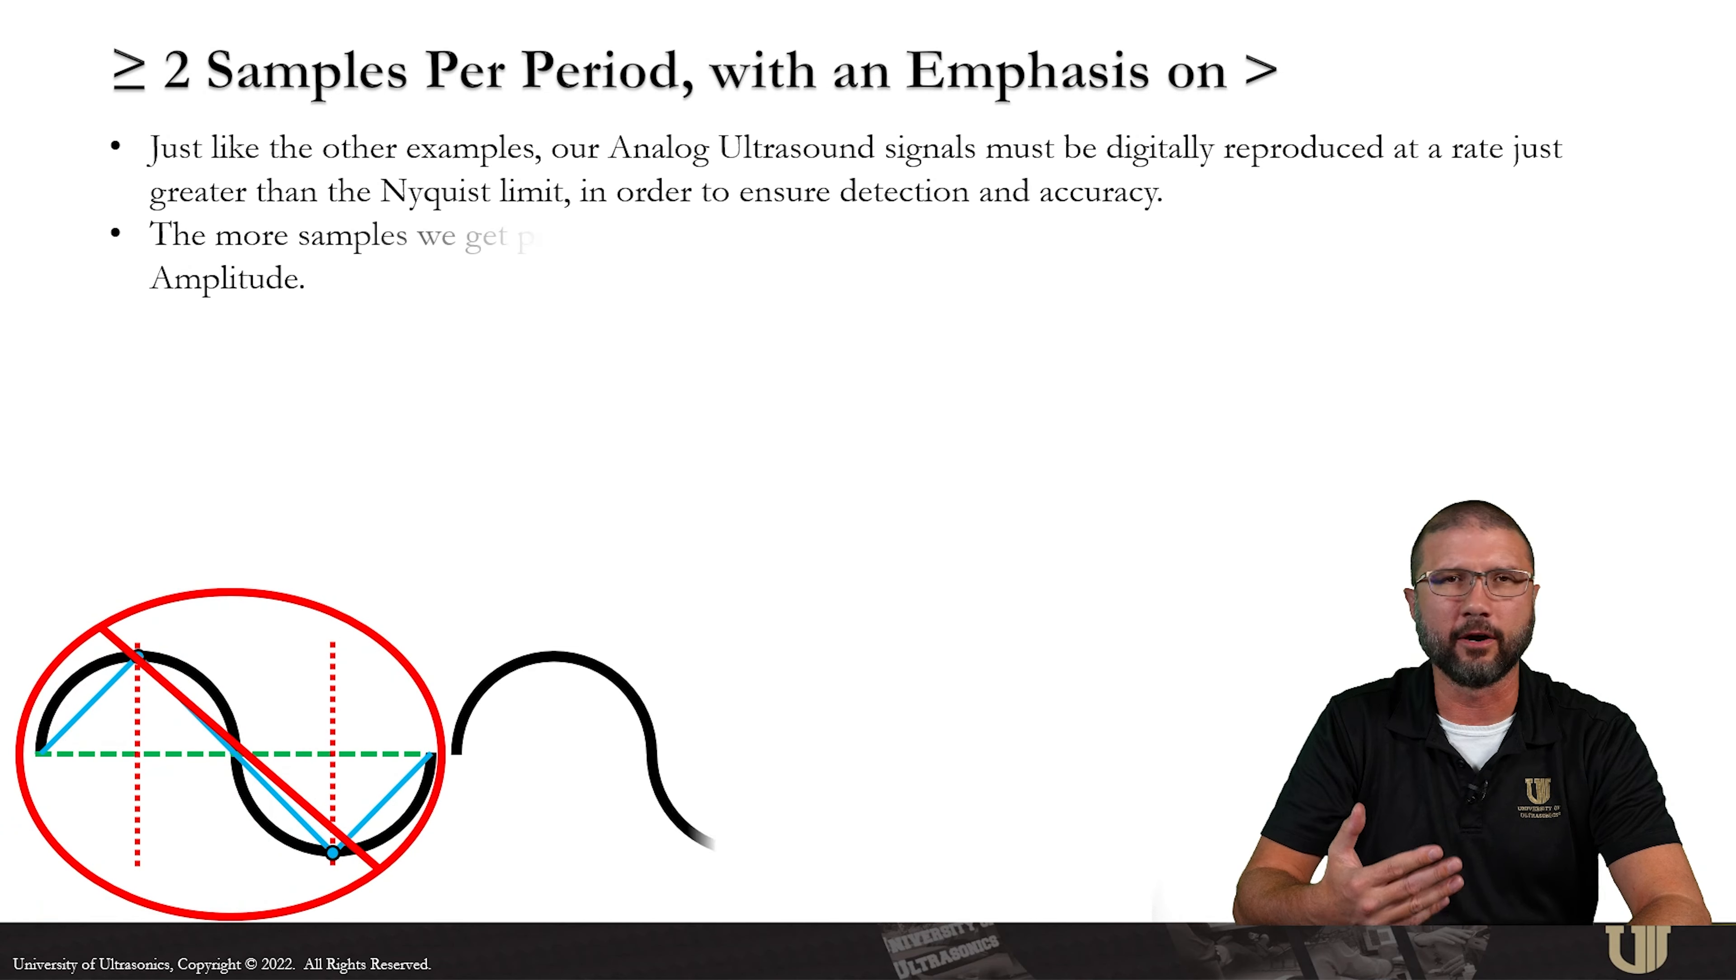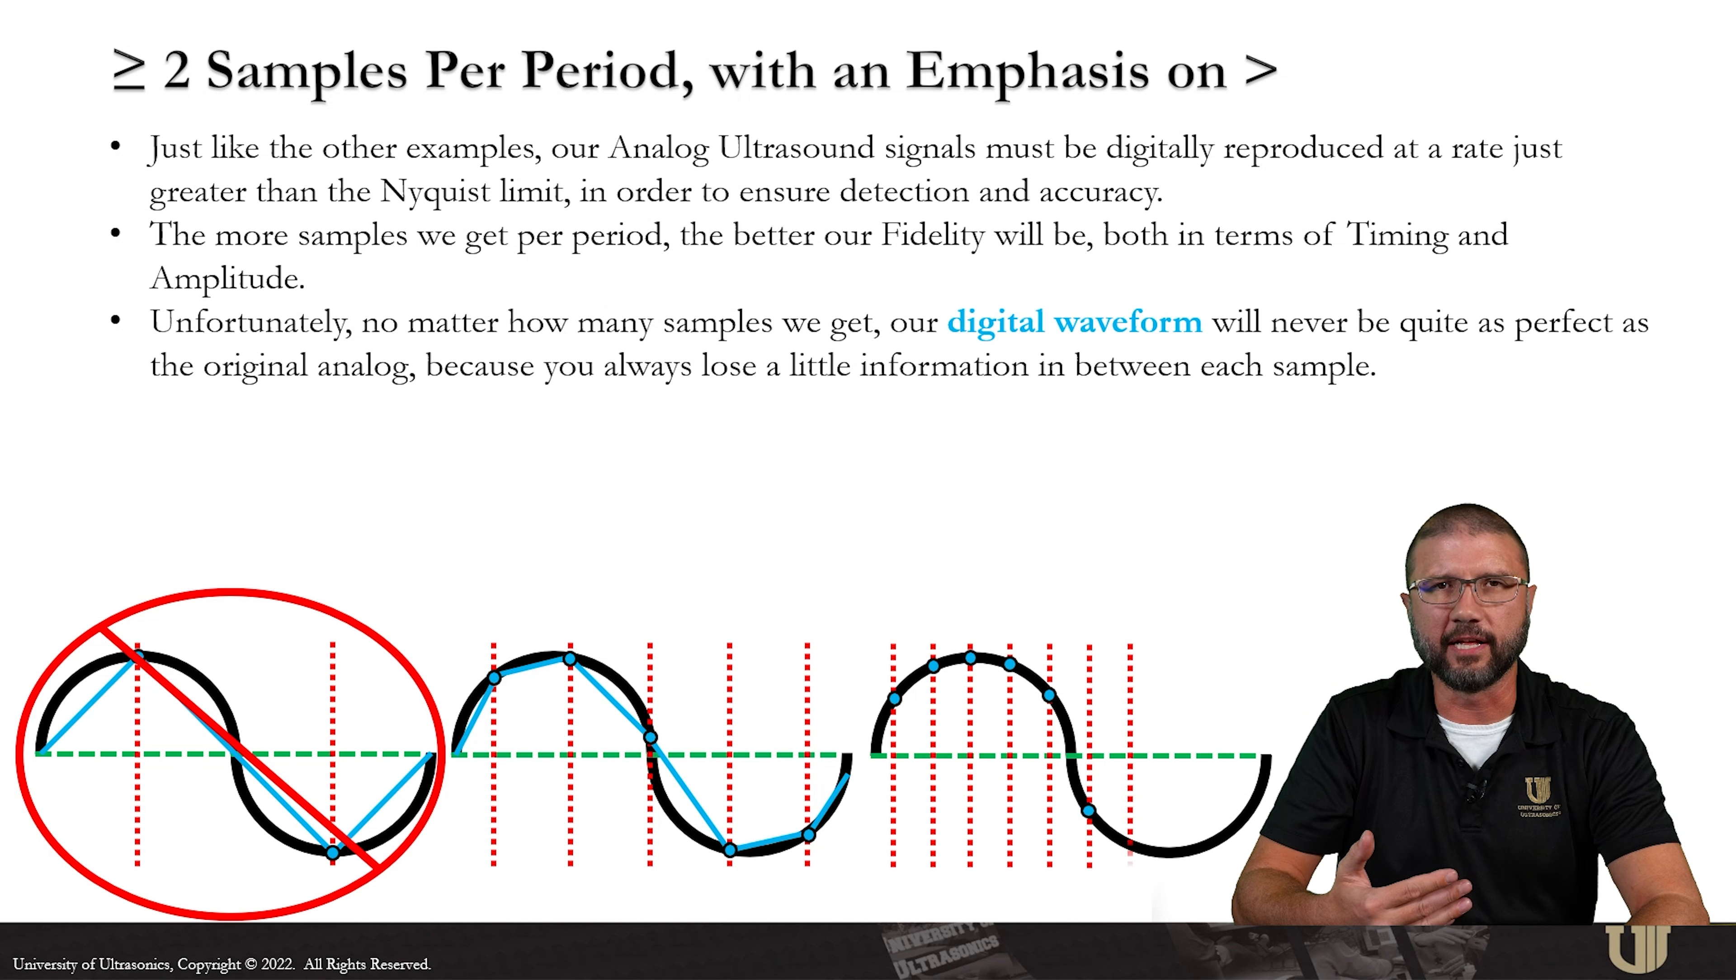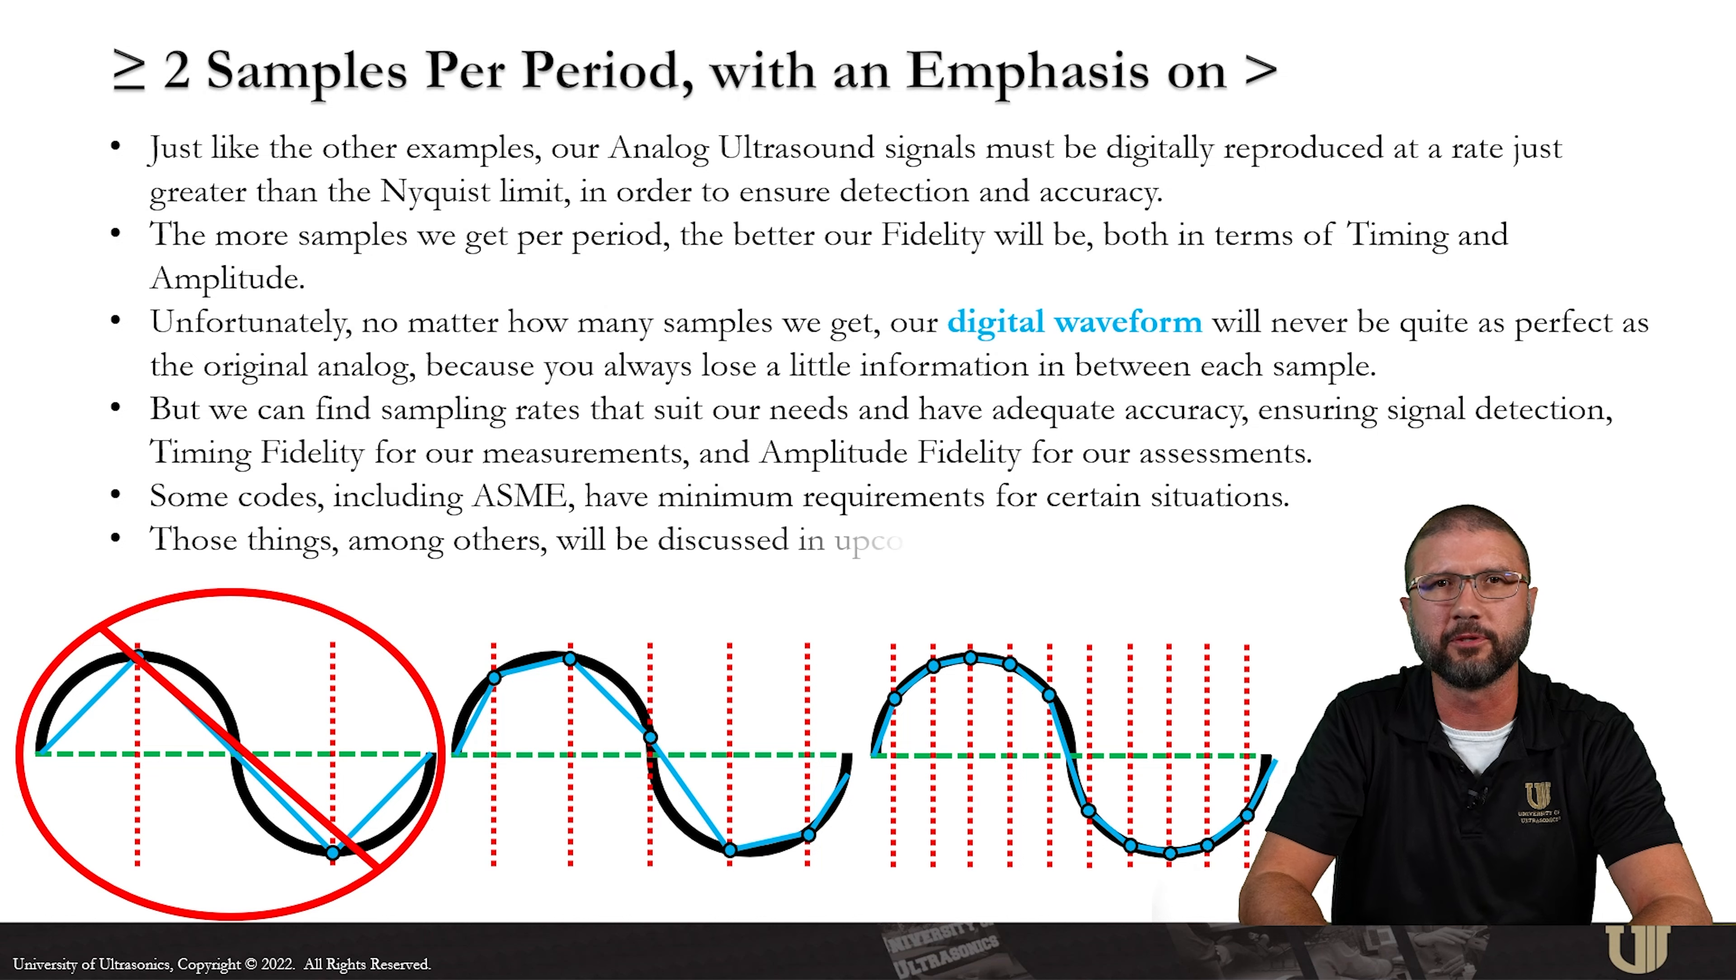Just like those other examples, our analog ultrasound signals must be digitally reproduced at a rate just greater than the Nyquist limit to make sure that we have detection and some bit of accuracy. The more samples we get per period, the better our fidelities will be both in terms of time and amplitude. But unfortunately, no matter how many samples we get, our digital waveform will never be quite as perfect as the original analog because you always lose a little bit of information in between your samples. But we can find sample rates that suit our needs and have adequate accuracy, ensuring signal detection, timing fidelity of our measurements, and amplitude fidelity for the amplitude assessments. Some codes, including ASME, are going to have minimum requirements for certain situations and those things and others we're going to talk about in future installments.